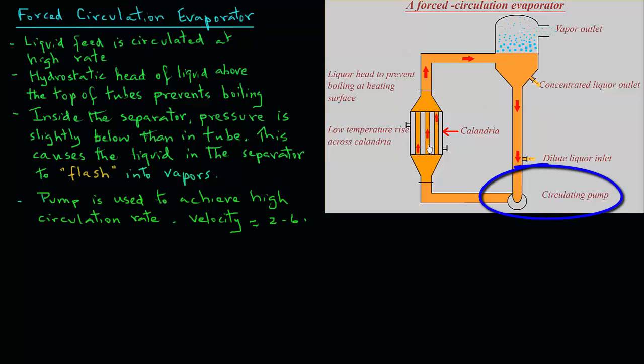The velocity of liquid inside the tubes is typically 2 to 6 meters per second. The residence time of the feed in the tubes is fairly short, 1 to 3 seconds.